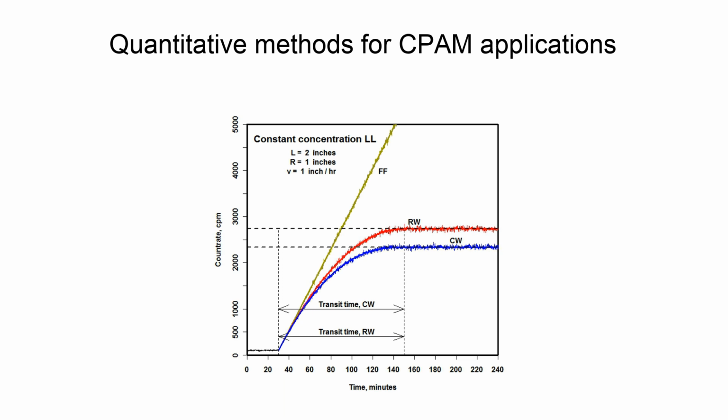It turns out that it is very useful to find the time integral of the concentration, as opposed to estimating the time-dependent concentration itself. It is essential to consider this choice for any CPAM application. In many cases, the integrated concentration is not only more useful in a radiological protection sense, but is also more readily accomplished, since estimating a concentration in, more or less, real time is difficult. For example, the total activity released from a plant stack over a time interval.